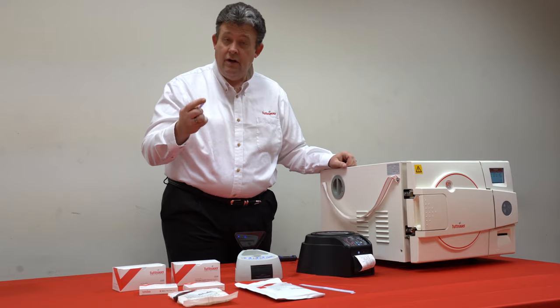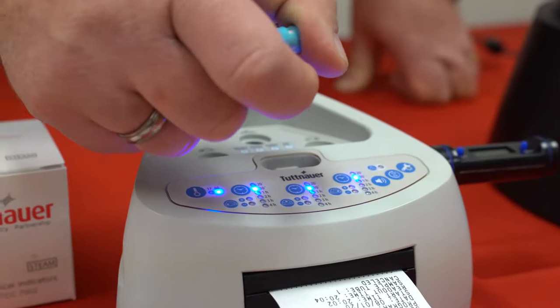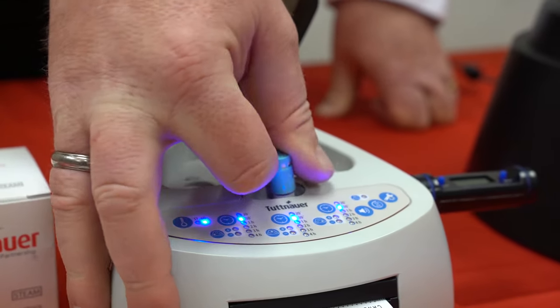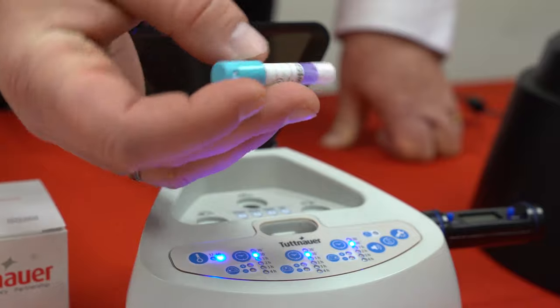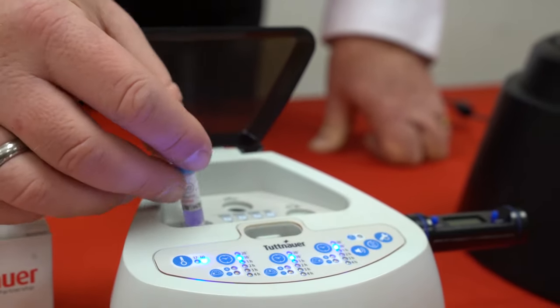After it comes out of your sterilizer, you're going to close the top. You're then going to crack the ampule — I go through it three times. After I crack the ampule, I'm going to mix the solution four or five times and put it in my biological incubator.